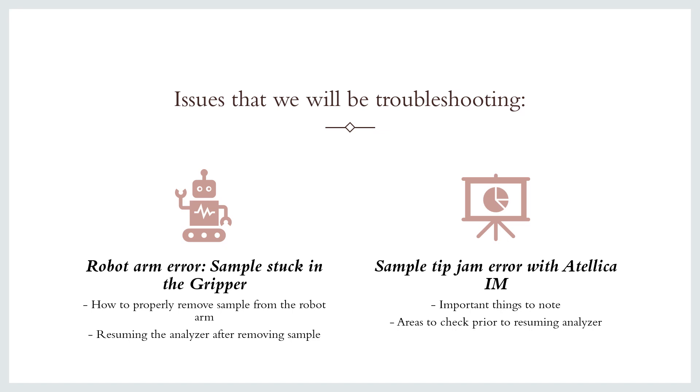The first issue we'll be troubleshooting is the robot arm error. This is where a sample is stuck in the gripper portion of the sample handler and you'll have to manually remove it to continue processing patient samples. The second issue we will be discussing is the sample tip error that commonly occurs with the IM module of the Atellica.